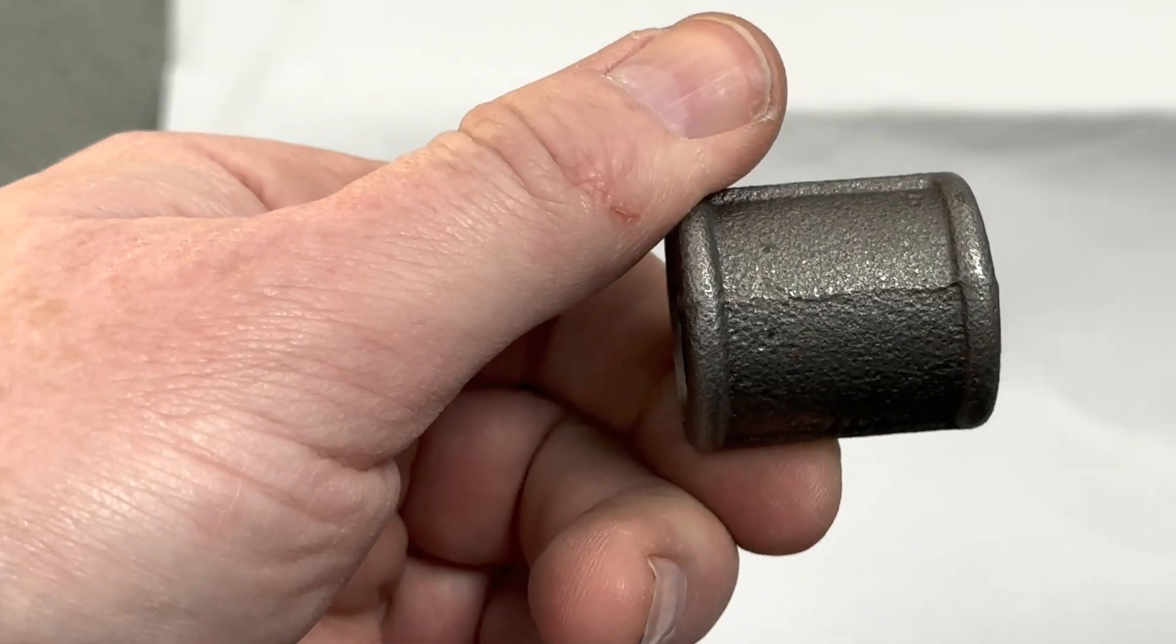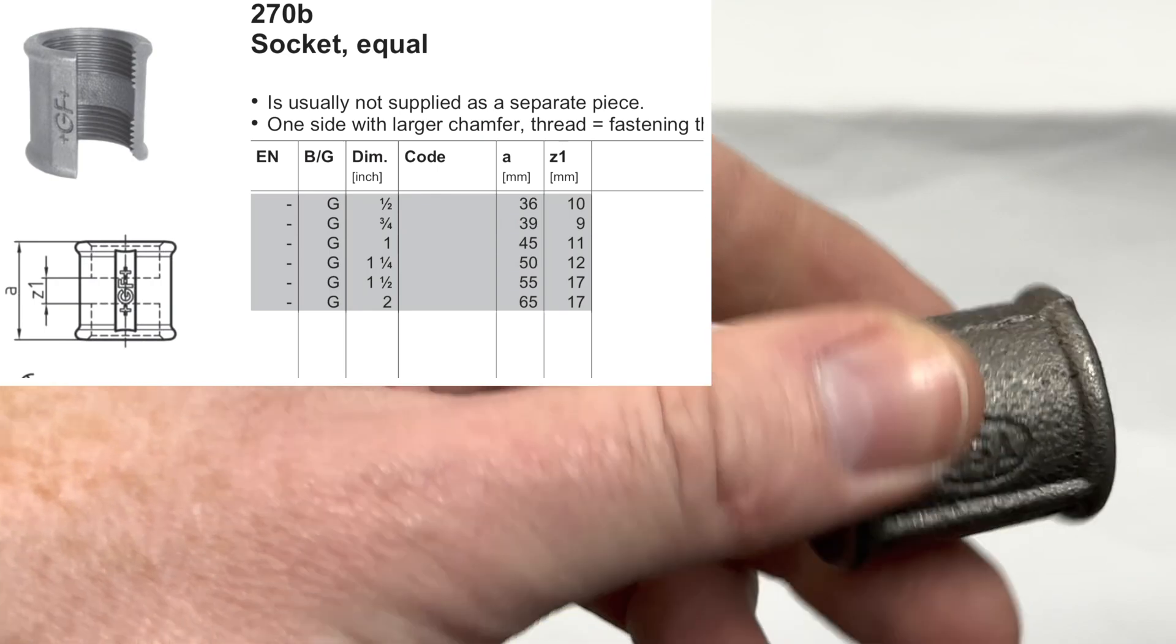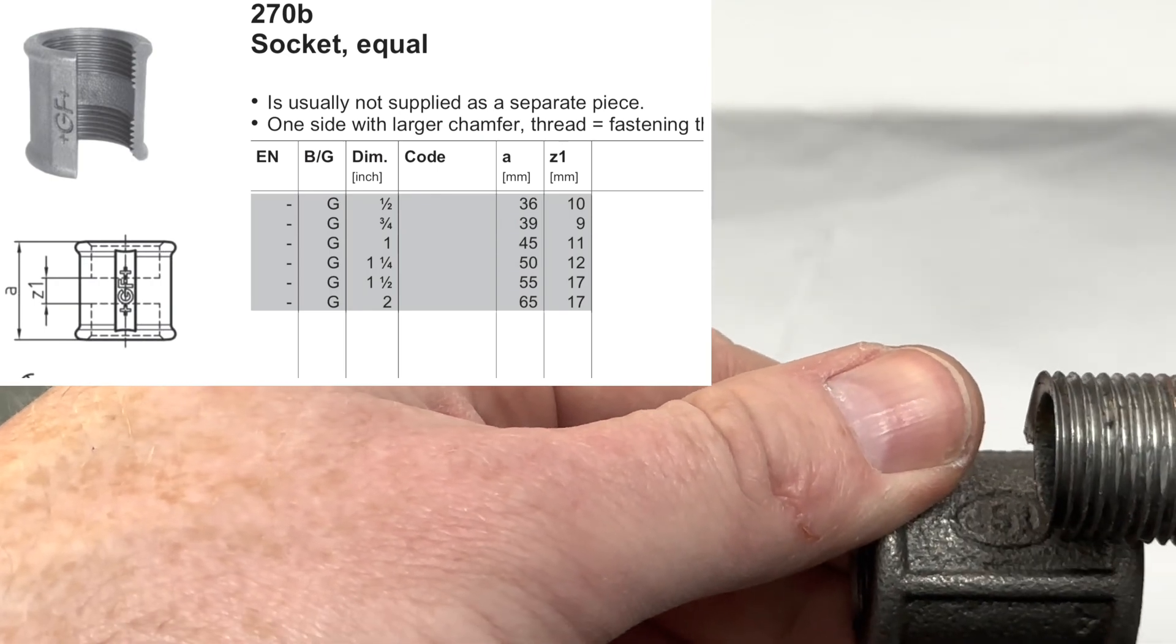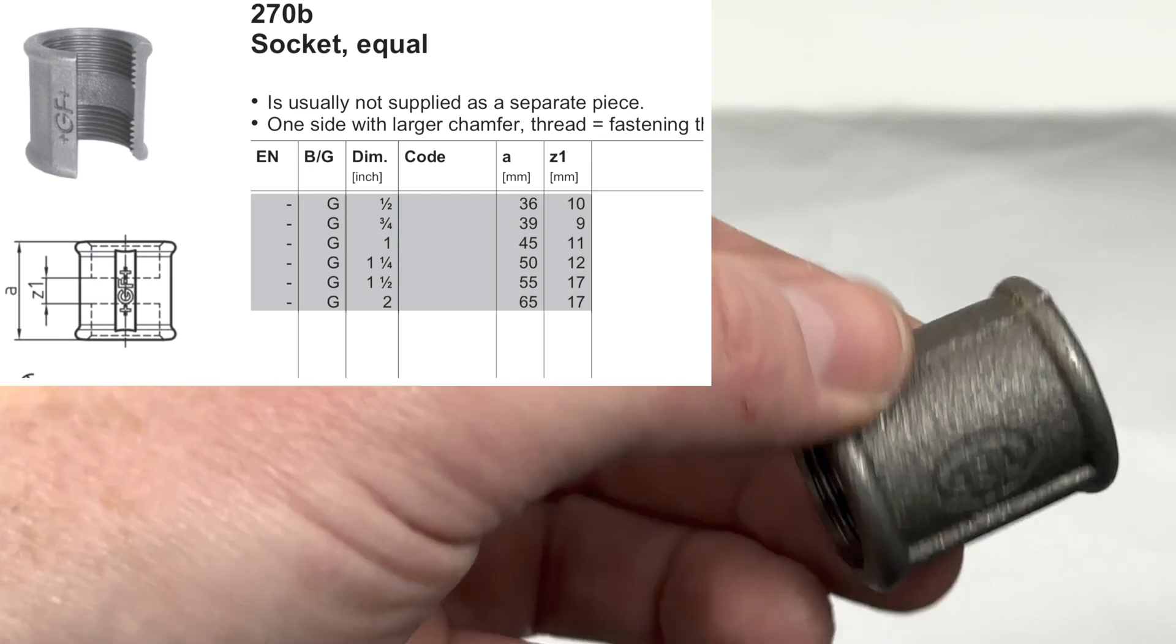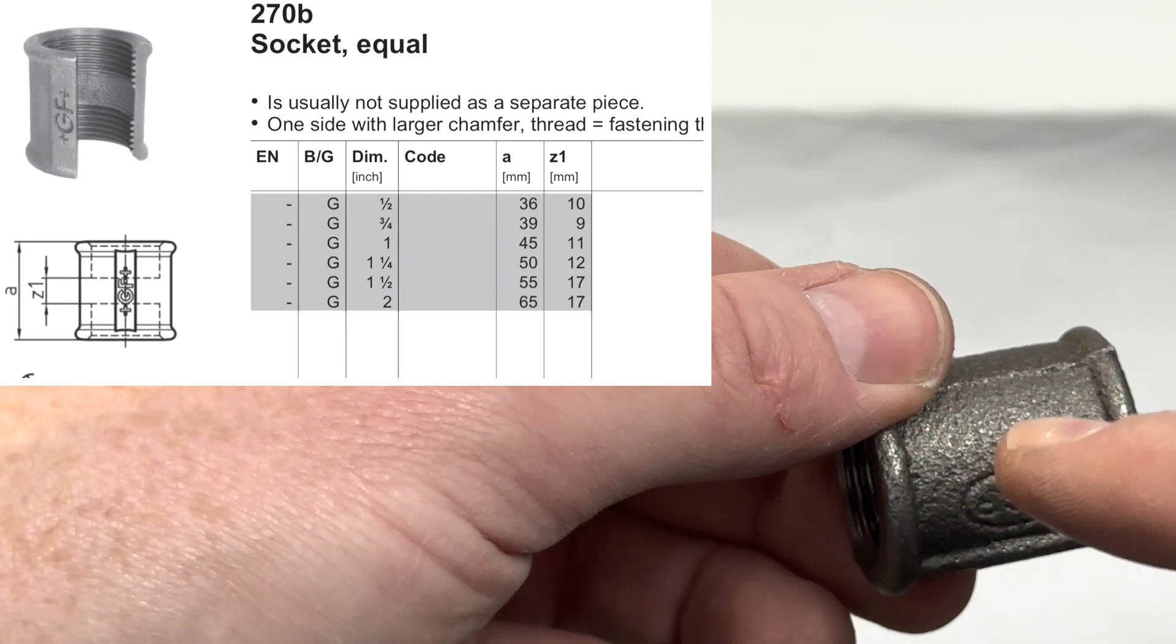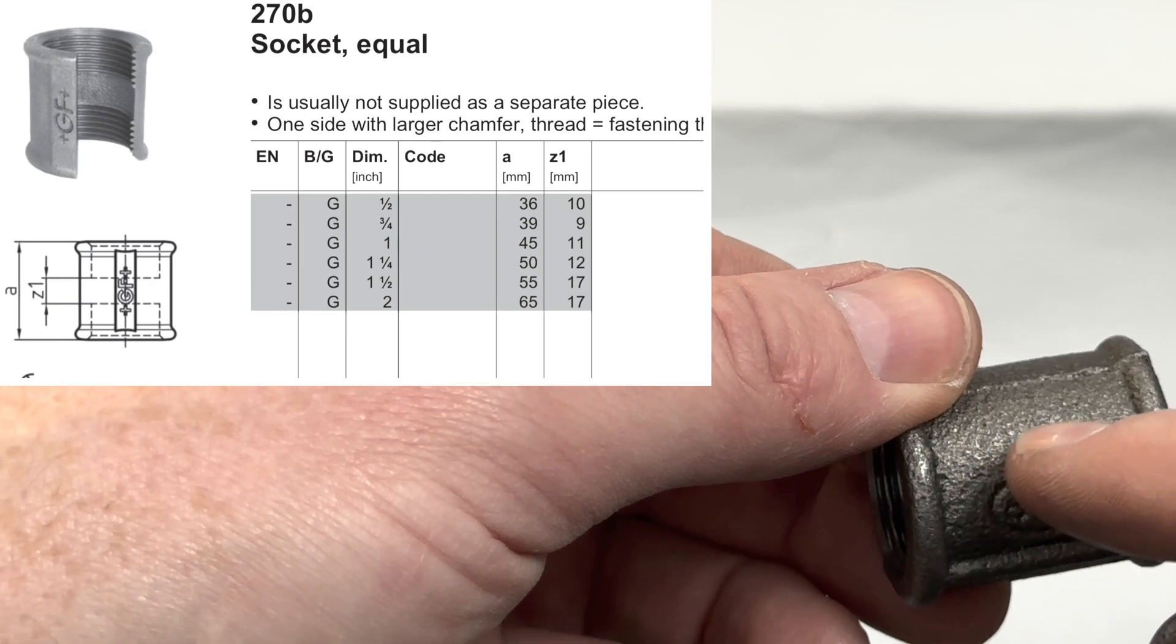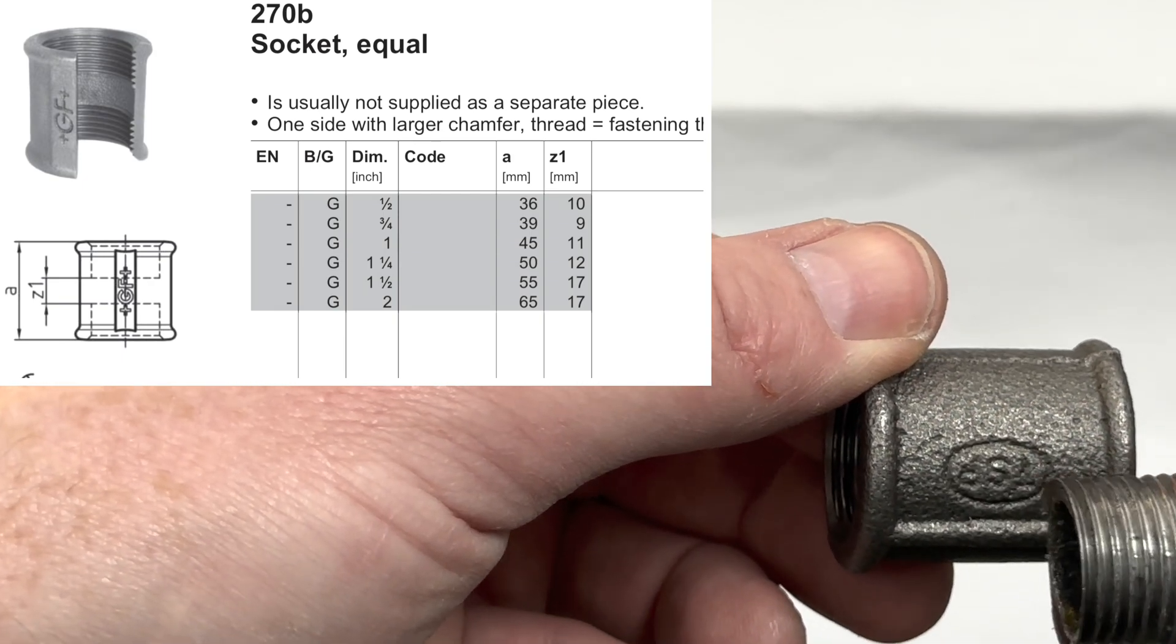Don't be deceived by sockets. The pipes don't meet in the middle. There still is a Z dimension. If you look at the technical charts, we can see that, for example, for this half-inch socket, there's a 10mm Z dimension in the middle.